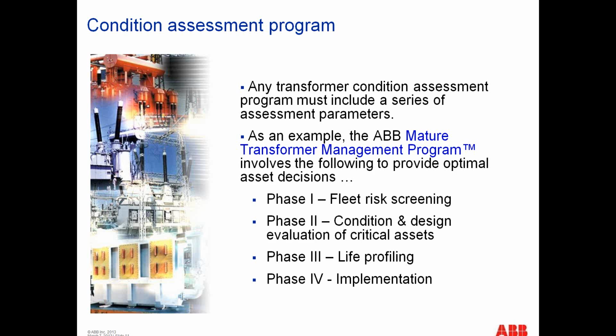A lot of these, for example, involve the cooling system. The core and coils of the transformer can last 50, 60 years, but a lot of times fans, pumps, even the radiators themselves might need to be replaced partway through that.